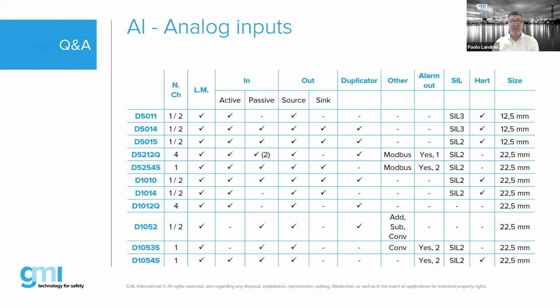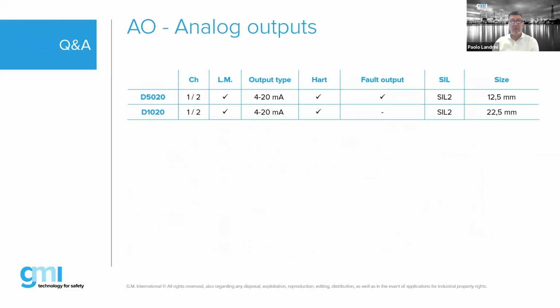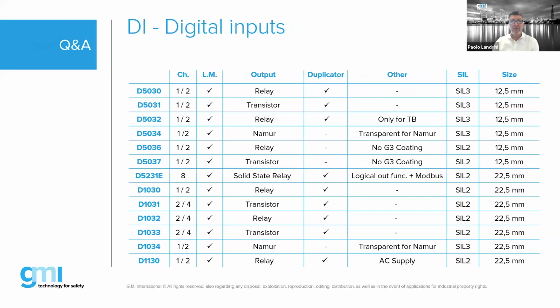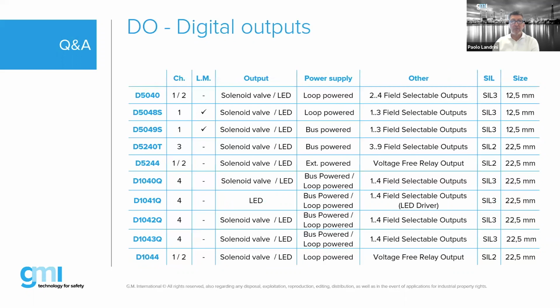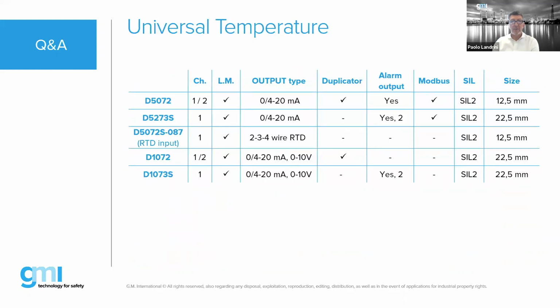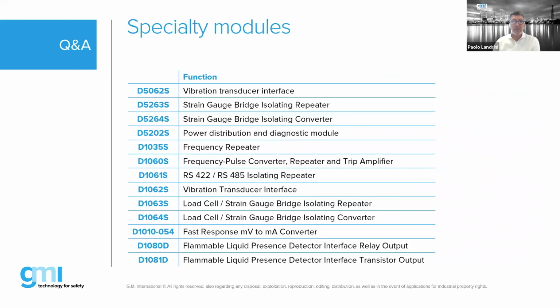Here, for example, is a list of the GMI barriers that are available. You can see there are many: analog input, analog output, digital input, digital output, universal temperature device, specialty barriers. As we discussed earlier, we have vibration, strain gauge, frequency, RS485, Modbus. So there's always a solution, but in very, very few cases are isolated Zener barriers used. I answered that question earlier in the recap, in the last question.